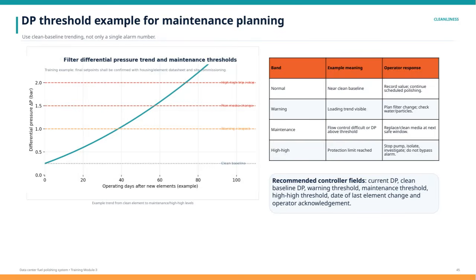Here we have an example of using differential pressure thresholds for maintenance planning. Instead of reacting to just a single alarm number, it's important to use clean baseline trending. This means tracking the pressure difference relative to a clean, baseline state over time, which helps identify early signs of filter loading. Look at the trend example here, showing how cleanliness gradually shifts from a clean element toward maintenance and even high alarm levels.